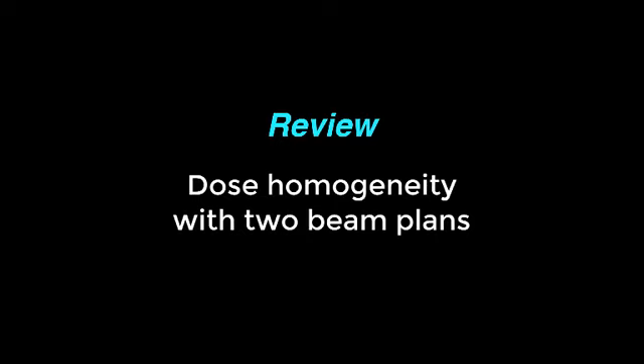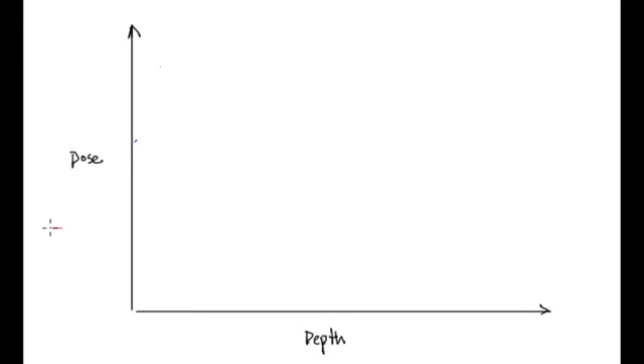So let's review some of the basic concepts in terms of dosimetry with two field plans, AP/PA, let's say. So I'm going to start here by imagining a beam coming in from this direction, and let's plot the depth dose curve for that beam. You get a sort of a smaller superficial dose, then it comes up and it falls off with depth, right? Now in TBI, actually, the surface dose is pretty close up here more, really. So let me redraw this. So it's more maybe like this. Okay, and then it falls off.